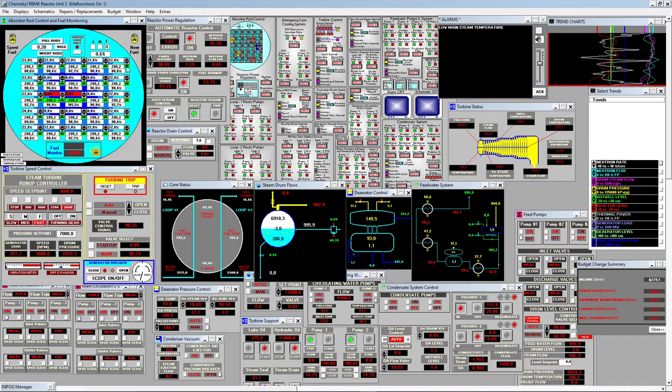One and two. Okay, after refueling one row out of the five rows, we get up to 53% fuel burn up. You see all these oscillations. We get two problems with these oscillations. I will connect back the sounds of the alarms. One is that you can get a too high neutron flux. The second one is that we get a neutron rate above 8%. So this is an alarm. I think 12% is scram. So acknowledge everything. And immediately we go up to 100% power.